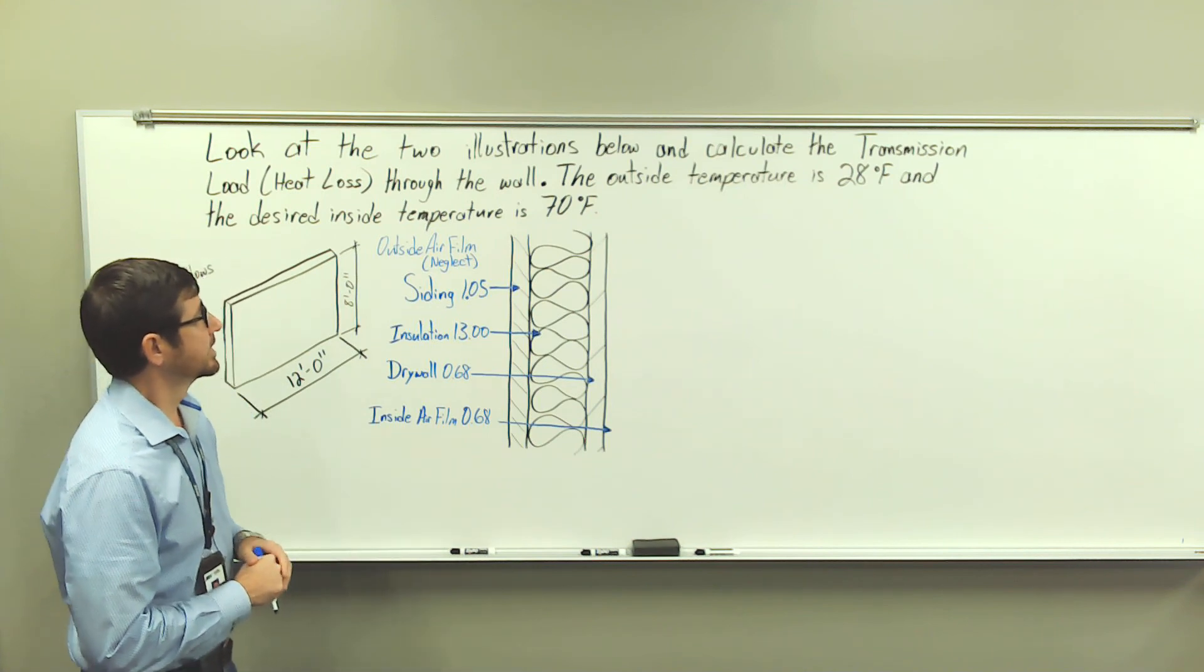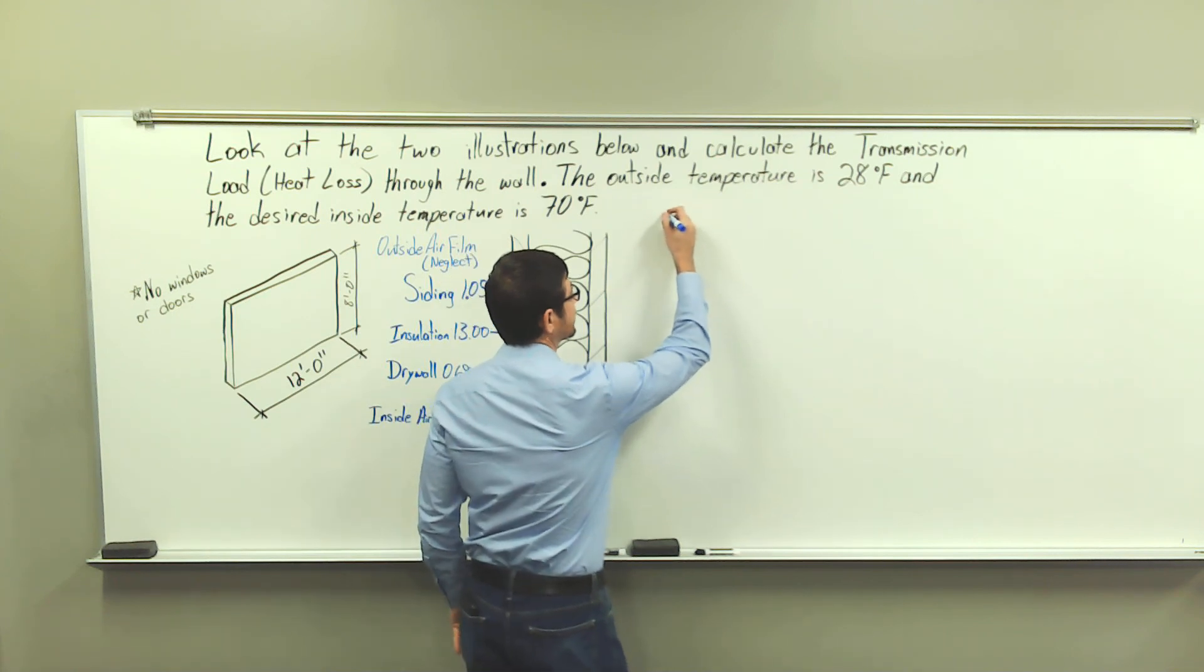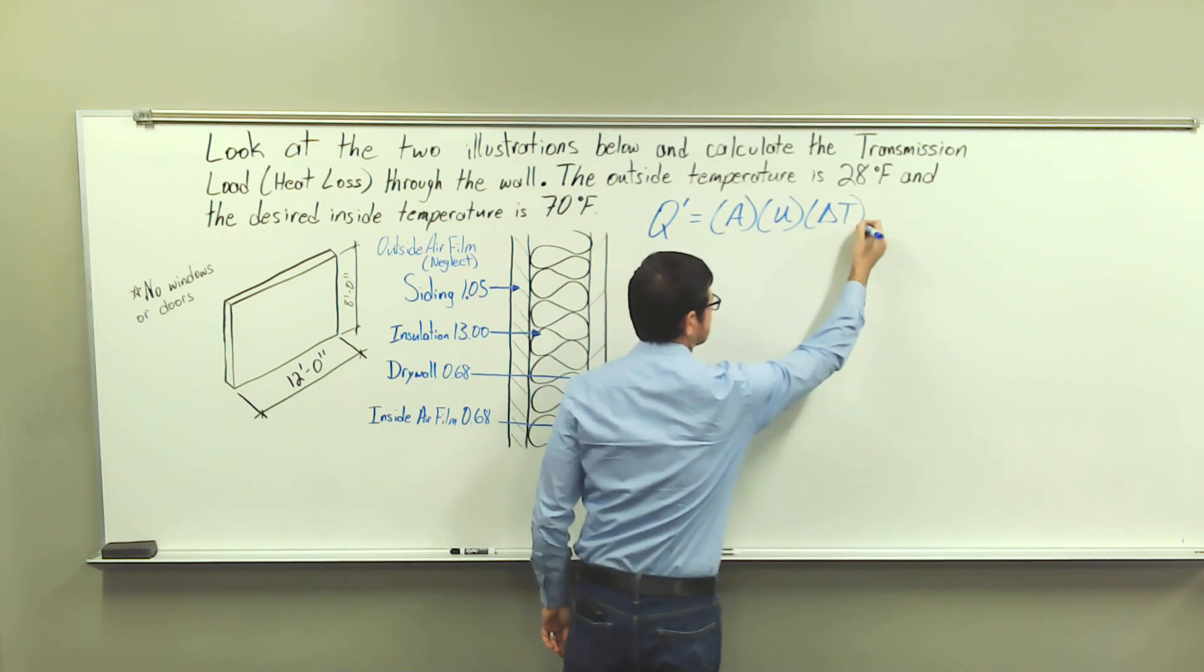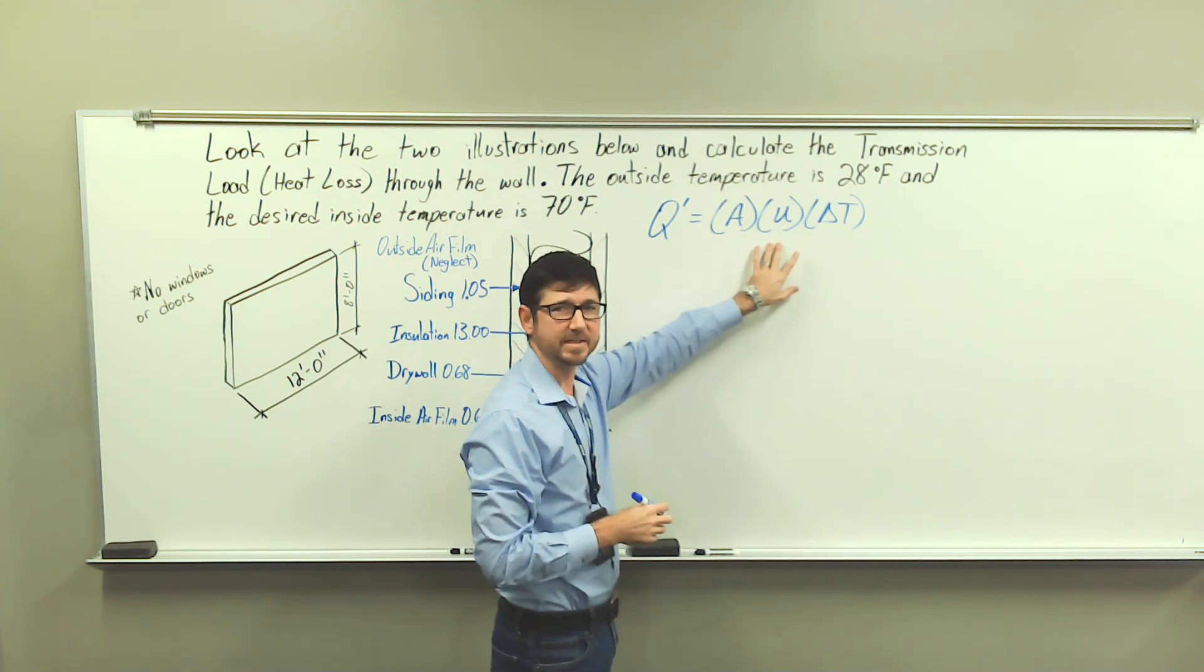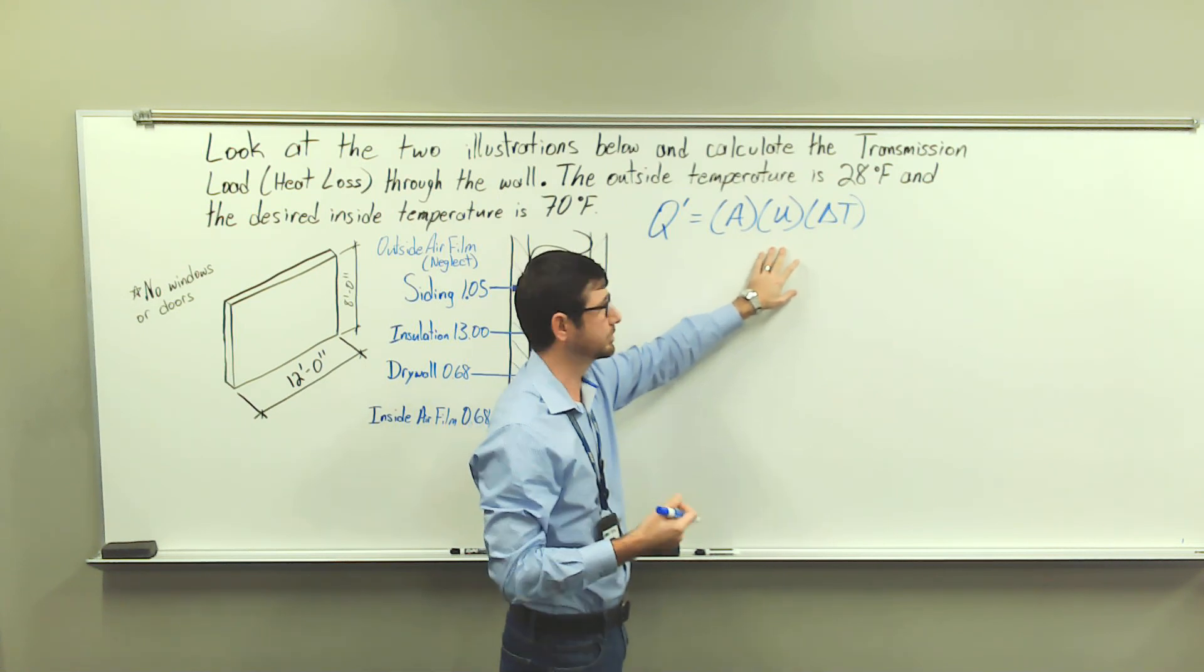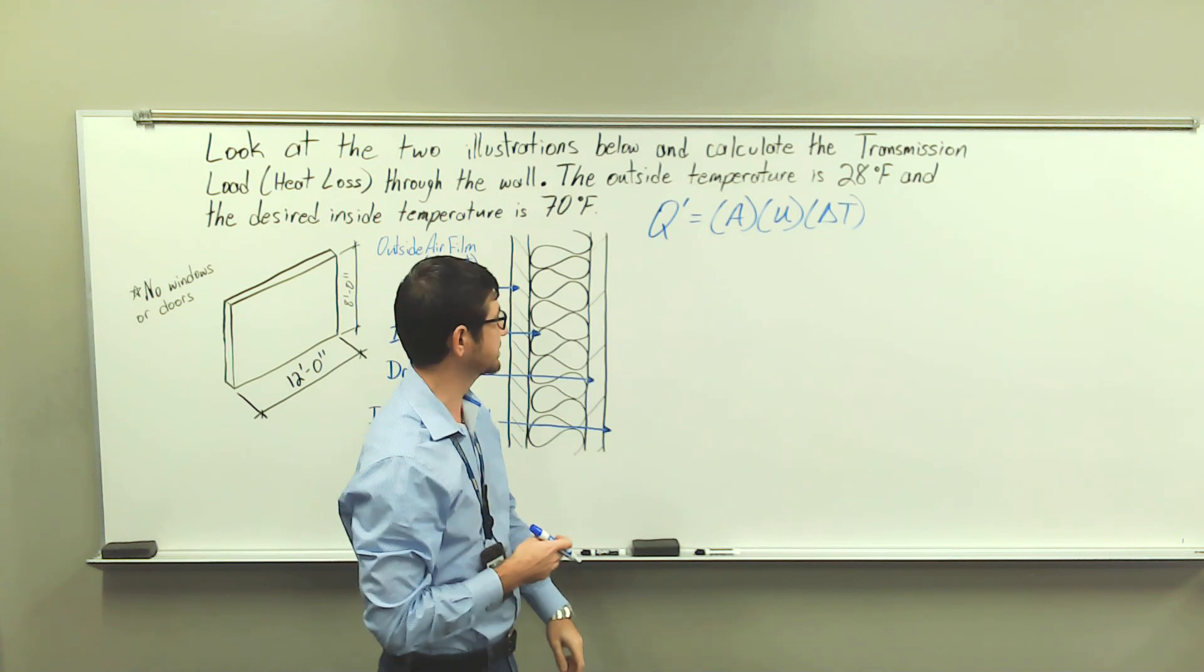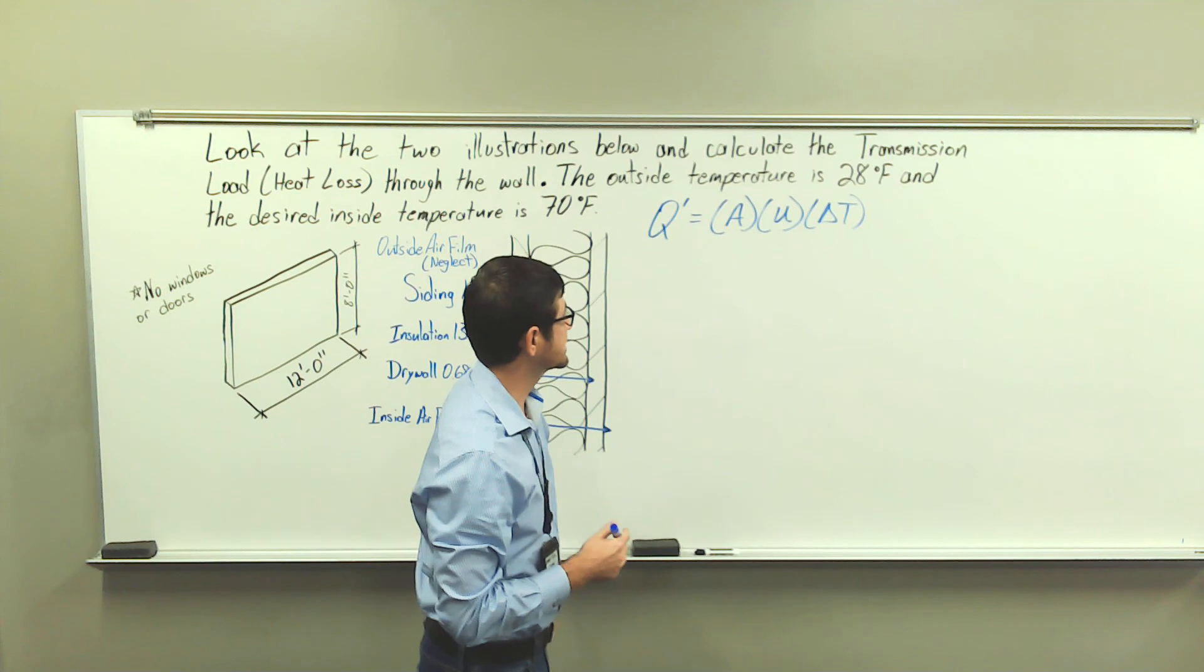Okay, so the equation to calculate the heat loss is Q' equals A times U times delta T. So A is the area of the wall, U represents the U factor which is the inverse of the total R value, and delta T represents the difference in temperature between the outside and inside temperature. So let's just go ahead and generate our three values here.